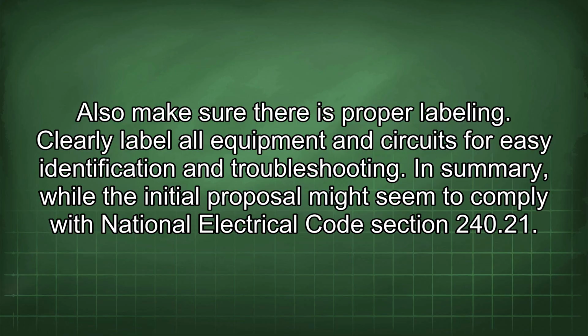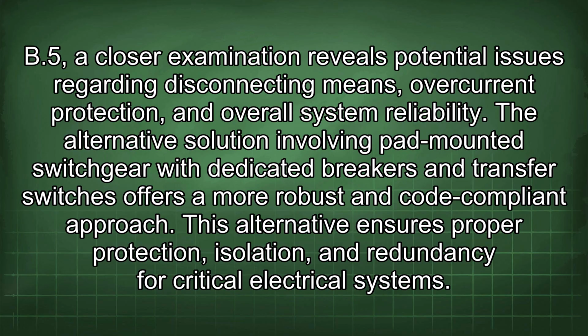In summary, while the initial proposal might seem to comply with National Electrical Code Section 240.21(B)(5), a closer examination reveals potential issues regarding disconnecting means, overcurrent protection, and overall system reliability. The alternative solution involving pad-mounted switchgear with dedicated breakers and transfer switches offers a more robust and code-compliant approach. This alternative ensures proper protection, isolation, and redundancy for critical electrical systems.